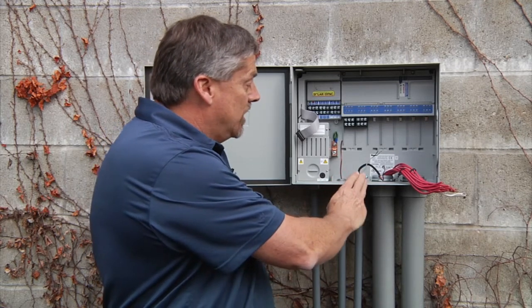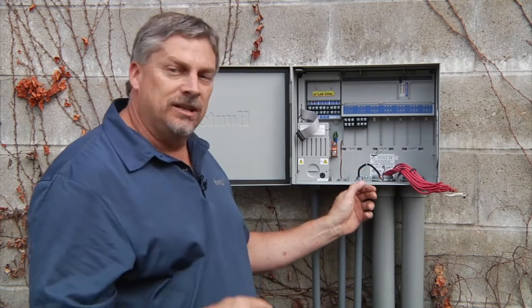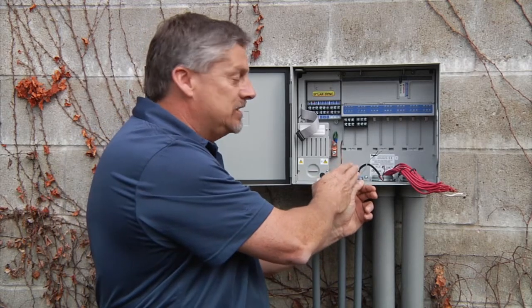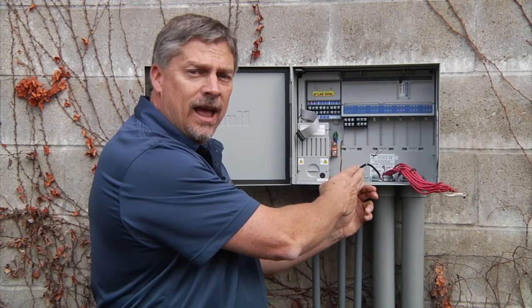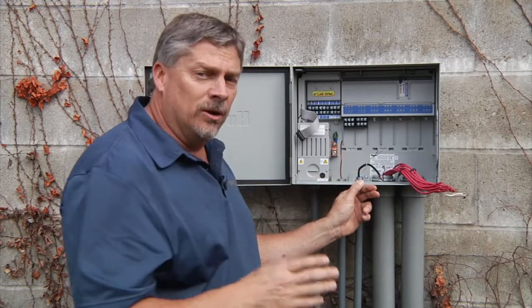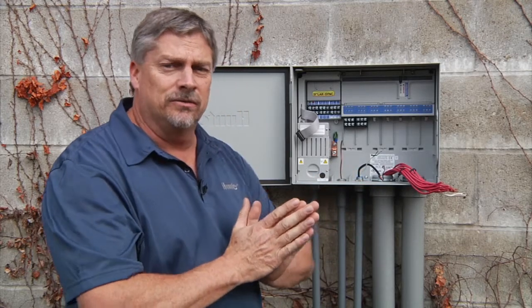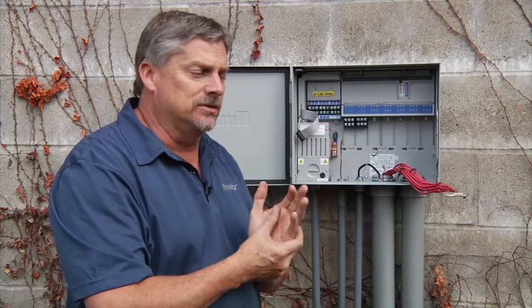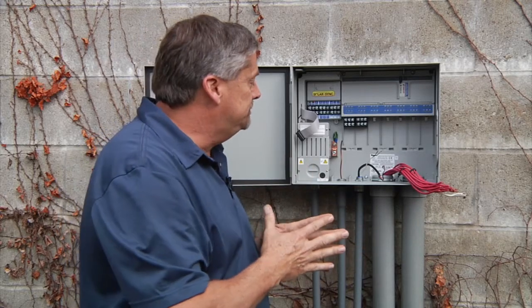The next conduit over is also a 1/2 inch or 13 millimeter, and we can utilize that for any sensors or communications needs that we might have. It's best to try to keep all communications in a separate conduit from the rest of the different wires to prevent any interference.